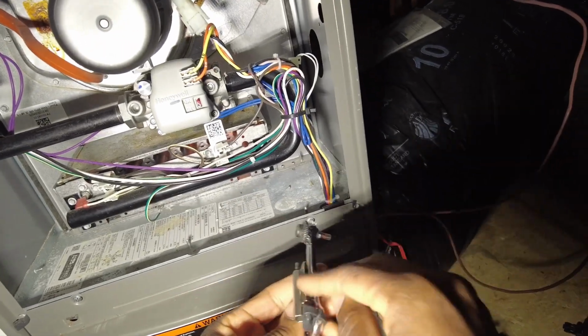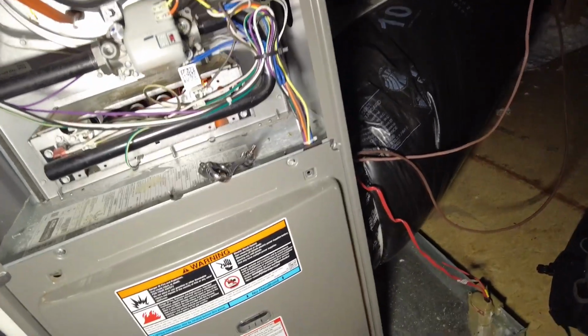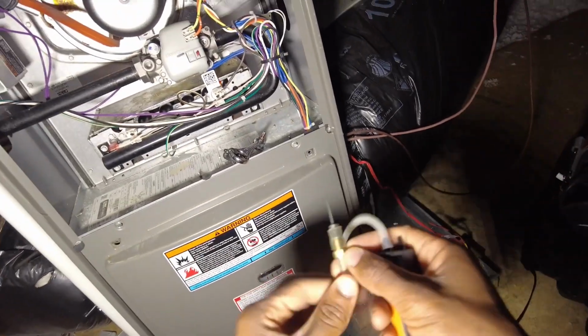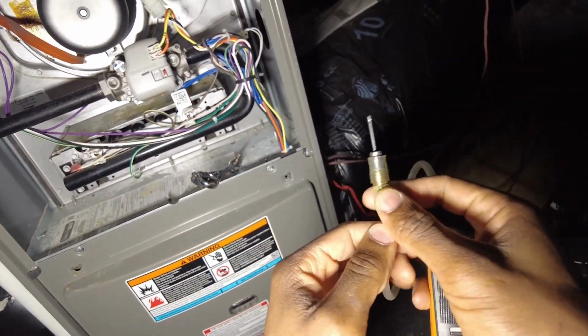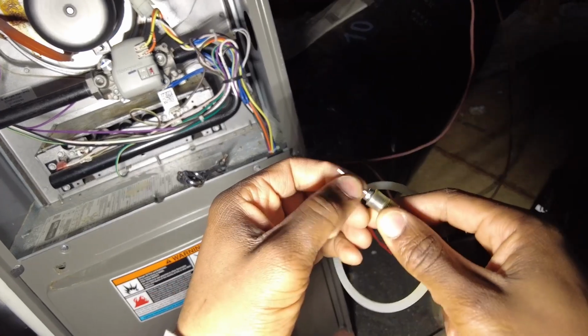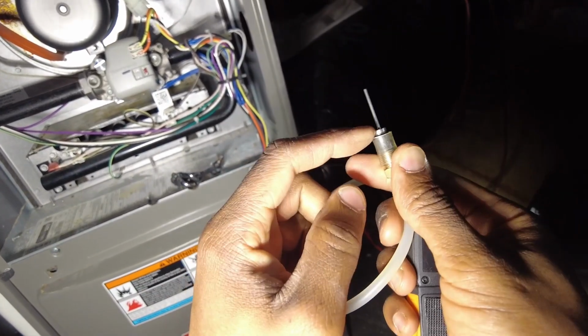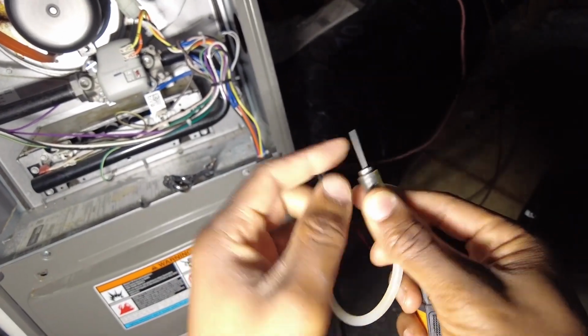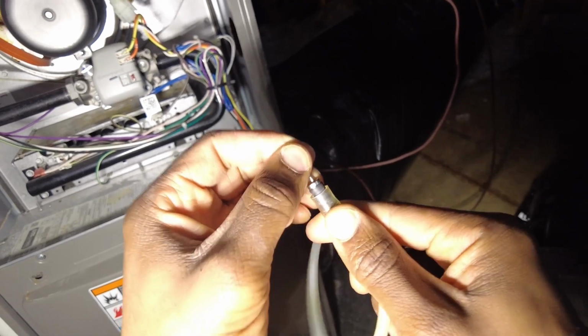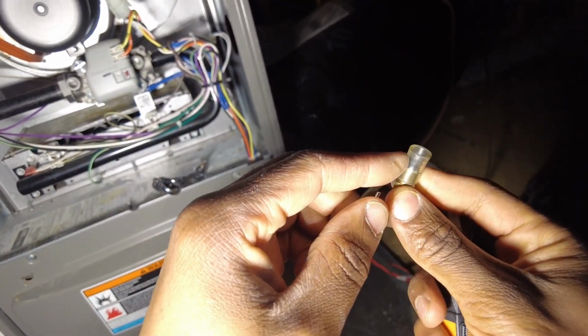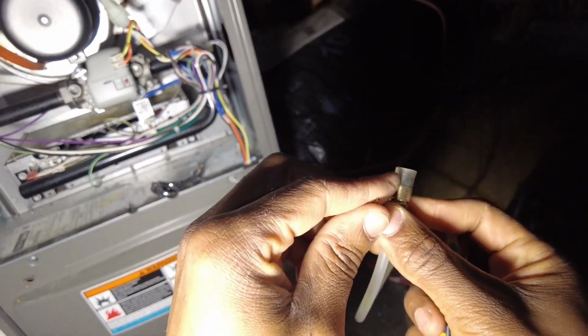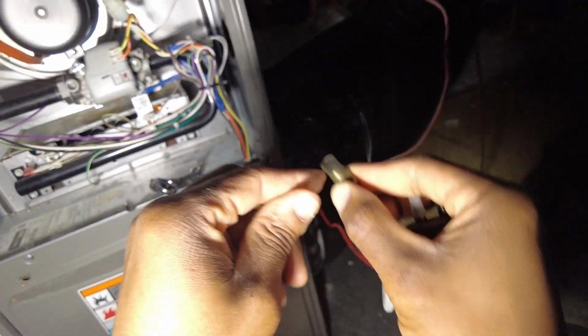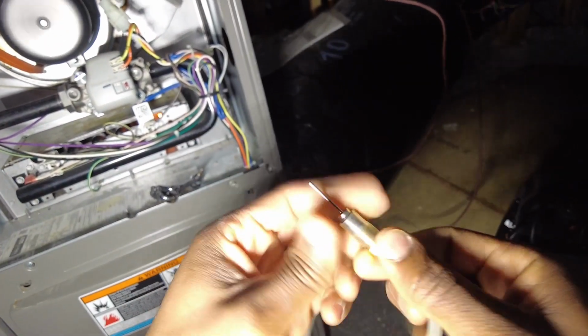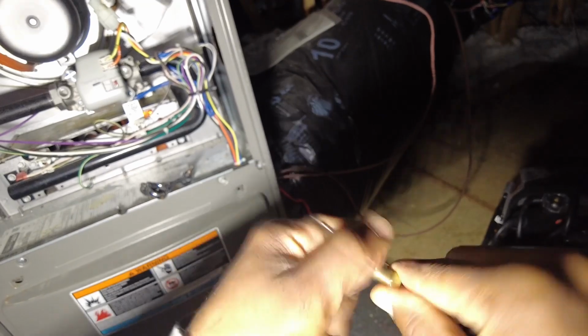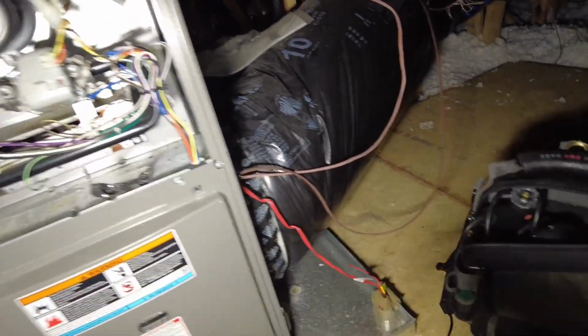That's why I've got that magnet on there, so that sticks. If you lose that, you're shot. You know, it's a bad day for you. I mean, it's not the end of the world, but you see how this has got multiple different fittings. So this here is a ball inflator. That's for static pressure. This here is for checking a different type of gas valve, which is you just slide this right over it. That's the one you can check live. And then the threaded brass fitting, that's for checking these.